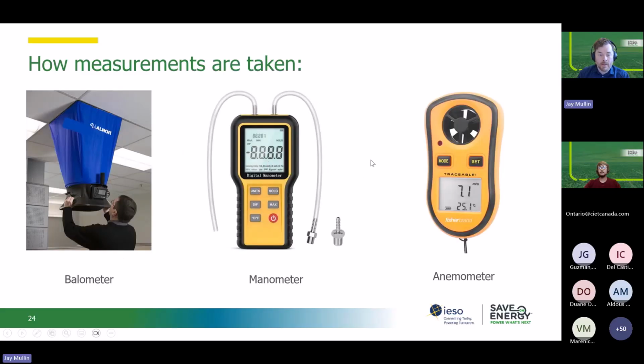How you can take measurements. A balometer is an air balancing instrument. It has a hood, an array of pitot tubes and sensors in the base. This is used to directly read airflow rates from intakes, outflows, ceiling, wall, floor diffusers. Manometers are a really useful tool for balancing the pressure. They measure pressure differential between two places, whether that's across ducts, before and after a filter within an airflow system, or even between inside and outside, between one room and another room as well. So they're really useful for pressure differentials.